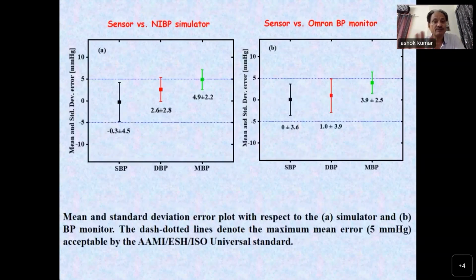So we have now developed the sensor which can be used. You can see the international protocol, sensor versus simulator, sensor versus Omron, and all are within the range of the international protocol. The protocol is that the error should be within 5 mmHg, and the standard deviation is plus minus 8 mmHg, less than that. So you can look at this, all is matching in between that. Only small errors are there. Yeah, please, next slide.